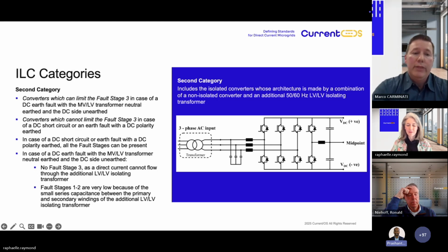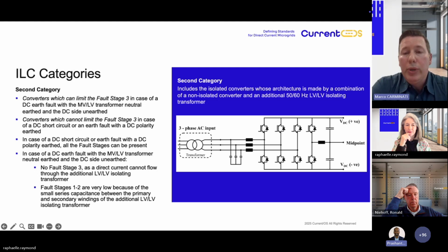In this category, the converter can limit the fault stage three in case of a DC fault with a medium voltage low voltage transformer neutral earthed and the DC side unearthed. But they cannot limit the fault stage three in case of a DC short circuit or an earth fault with a DC polarity, usually the negative, earthed. In case of a DC short circuit or an earth fault with a DC polarity earthed, all the fault stages, so the transient, one, two, and the third, can be present, still according to the ratio between inductances and capacitances.